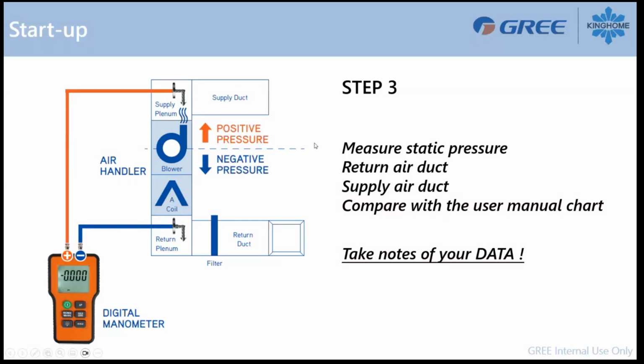So if you are using only one tube, you will have to add those numbers together to have your total static pressure. But make sure you compare your data with the chart inside the user manual. This is really important.